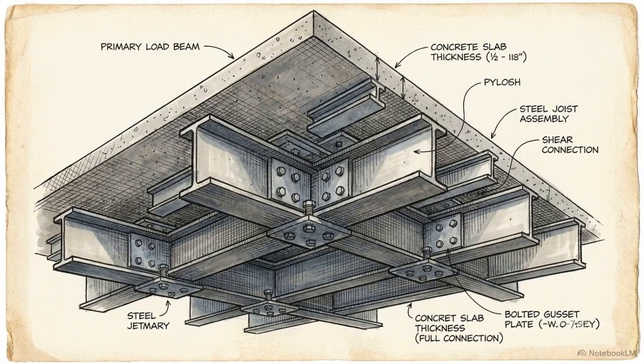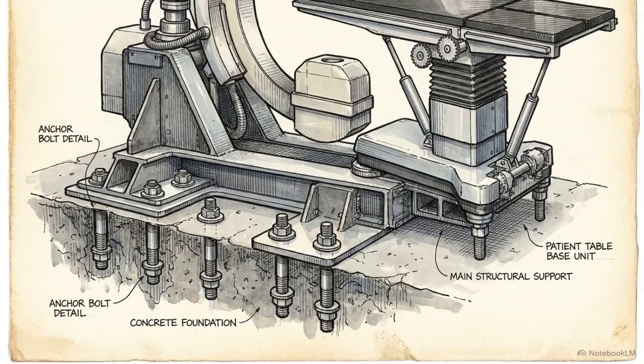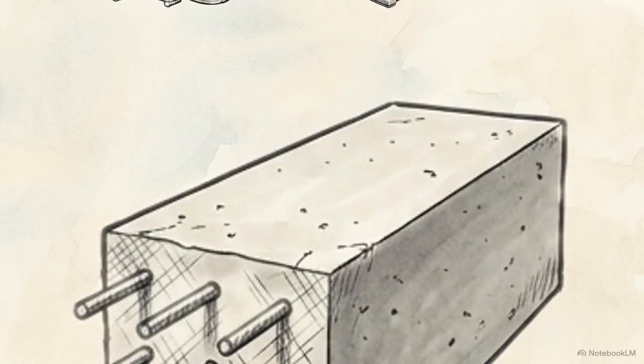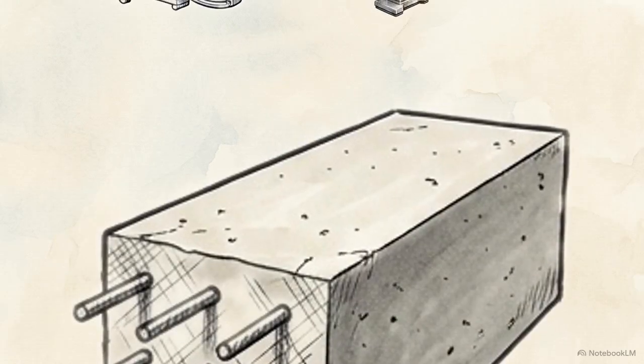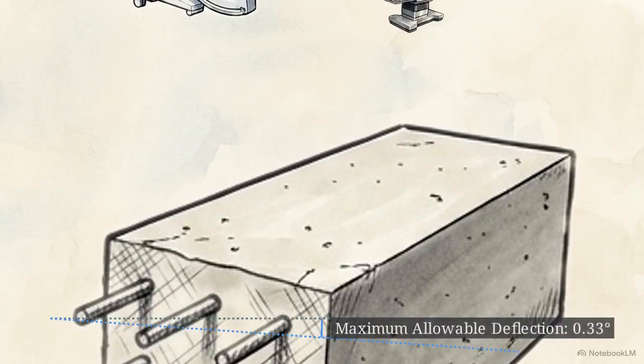Beyond radiation containment, the shell must support immense structural loads. The C-arm gantry and the motorized patient table weigh several thousand kilograms, generating extreme static and dynamic stress on the building's frame. This diagram illustrates strict structural tolerances. Under maximum load, floor slab deflection cannot exceed 1/3 of a degree. This absolute rigidity is mandatory.